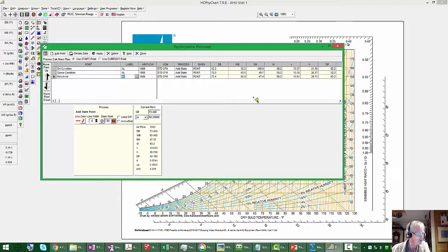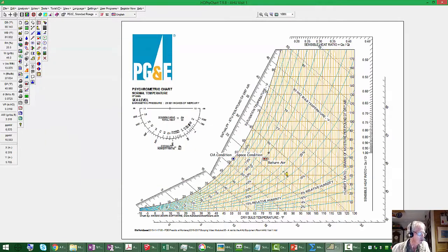Now, as an aside, there's actually a way we could have figured out about how much moisture was added to the air by the people in the building. For the time being, I'm not going to go into that, just to keep things moving here and not get too far off in the weeds. But basically, what that means is there's our return condition, okay? And basically, the decision about whether we want to use outdoor air or return air in a cooling process, it comes down to what's the energy difference. In other words, you want to cool the air that has the least amount of energy.